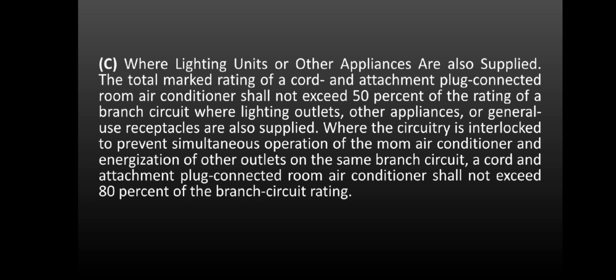C. Where lighting units or other appliances are also supplied, the total marked rating of a cord and attachment plug connected room air conditioner shall not exceed 50% of the rating of the branch circuit, where lighting outlets, other appliances, or general use receptacles are also supplied. Where the circuitry is interlocked to prevent simultaneous operation of the room air conditioner and energization of other outlets on the same branch circuit, a cord and attachment plug connected room air conditioner shall not exceed 80% of the branch circuit rating.